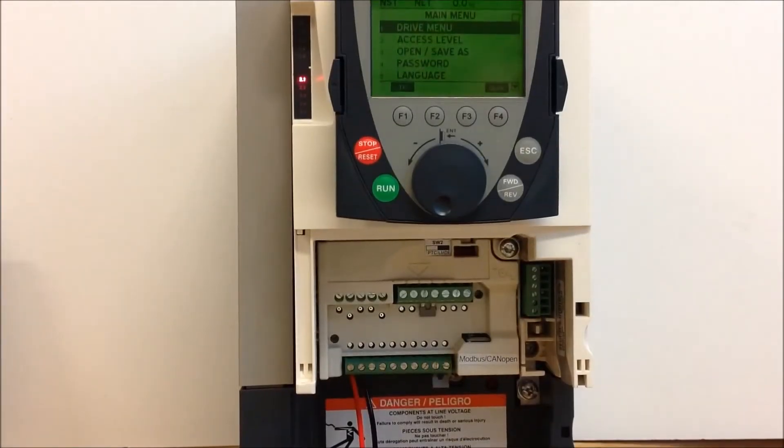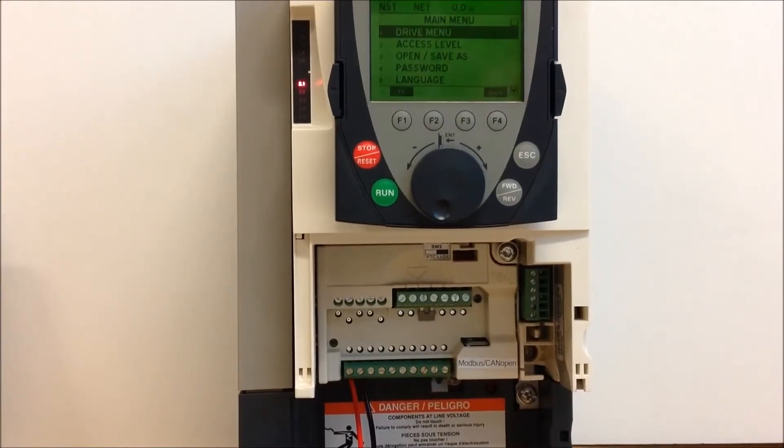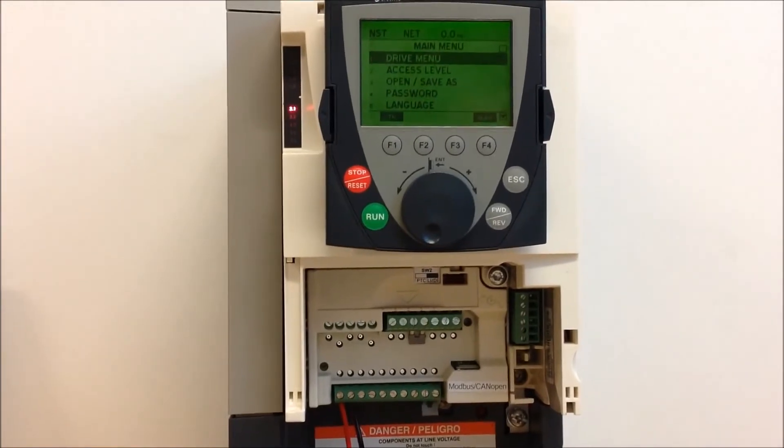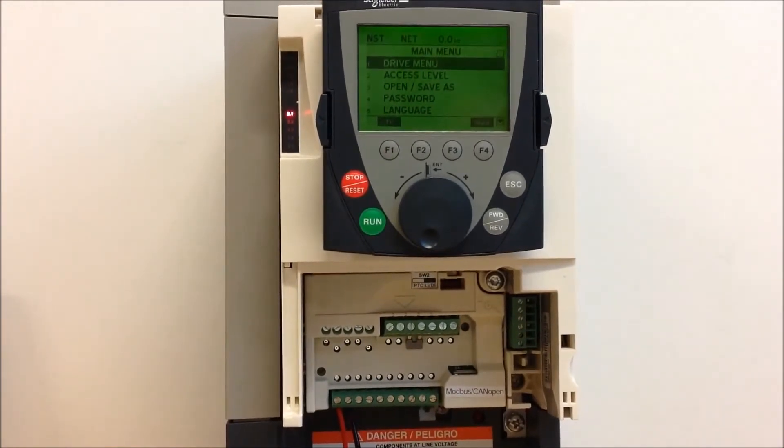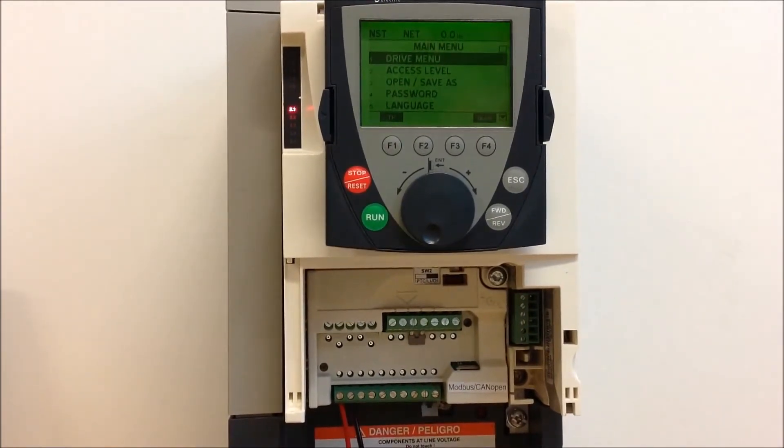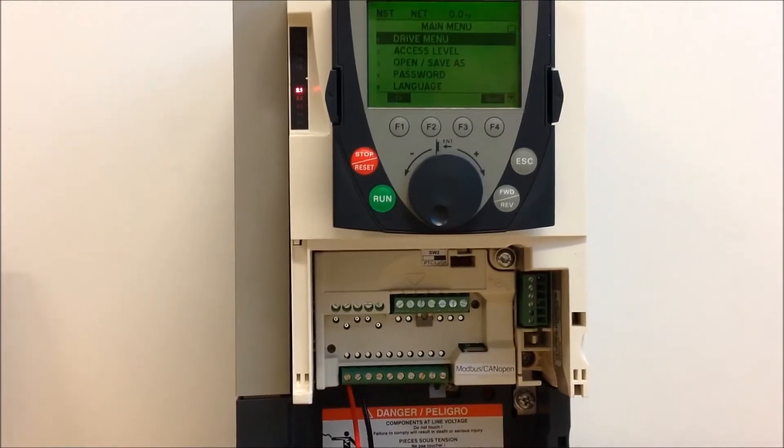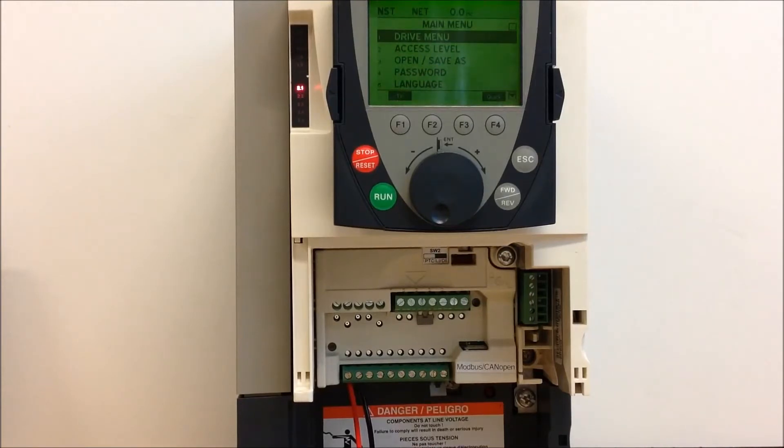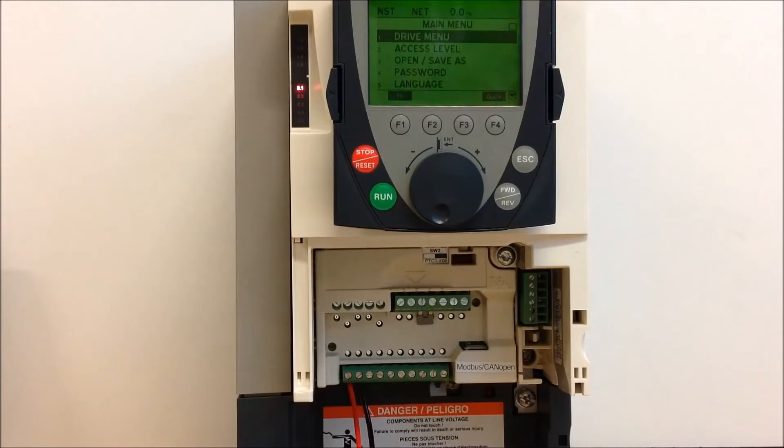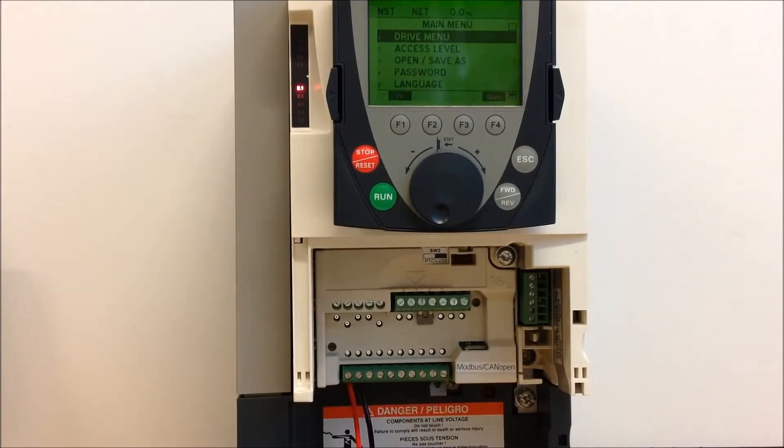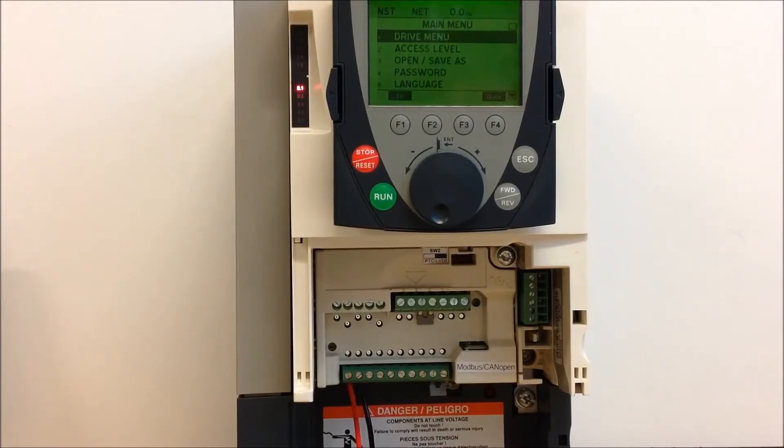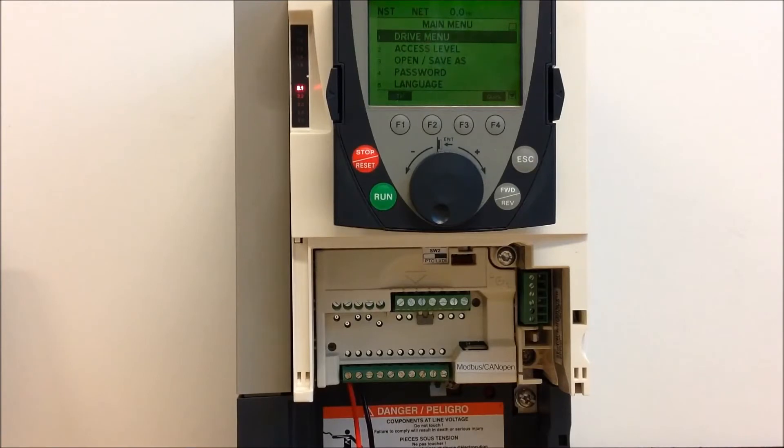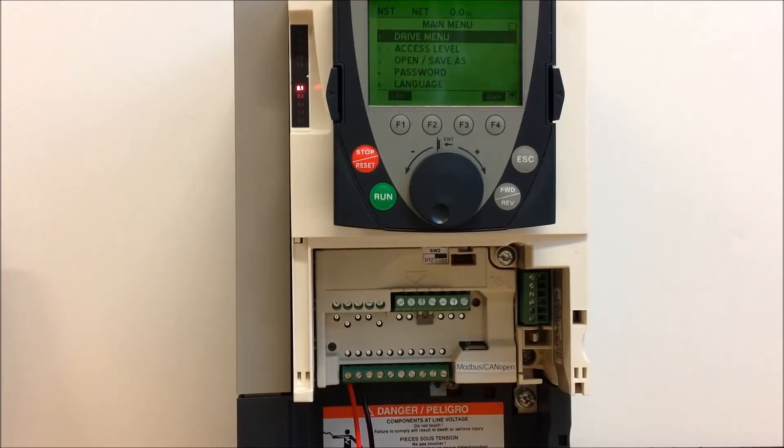So if you want to set your setpoint with your keypad's dial, you'll need to make sure that your PID feedback is programmed. But more importantly, you also have to make sure that your internal PID is set to no, because internal PID is basically where you actually tell the drive what the setpoint is. It's just one parameter you have to adjust every single time you want to change it, and it's in a specific menu. If you want to use a keypad HMI, then please do the following.